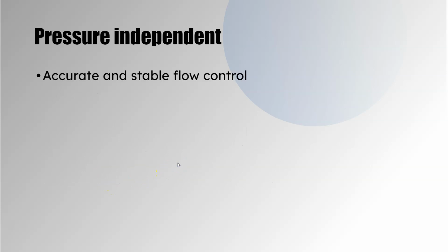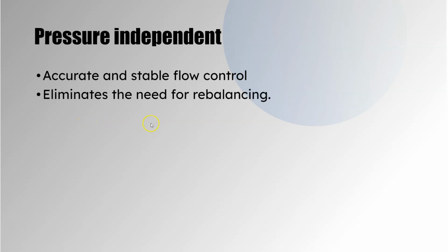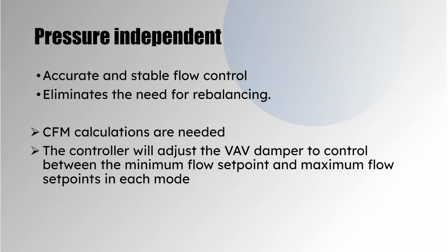And it's all based on temperature. Pressure independent is different. It's accurate and stable flow control. It eliminates the need for rebalancing. CFM calculations are needed, so we are going to calculate how much air is going through there. It's the same principle, but it's based on CFM calculations, airflow calculations, right? You're going to have a minimum airflow set in the controller and a maximum airflow set in the controller. And you're going to modulate between those two set points, those two flow set points, based on the room temperature. As the room gets warmer, it's going to modulate more to the maximum CFM. As it gets colder, it's going to modulate down to the minimum CFM. But you need some air, even if the room is cold. You need air circulating in there to do air changeouts, or else the air gets stale.